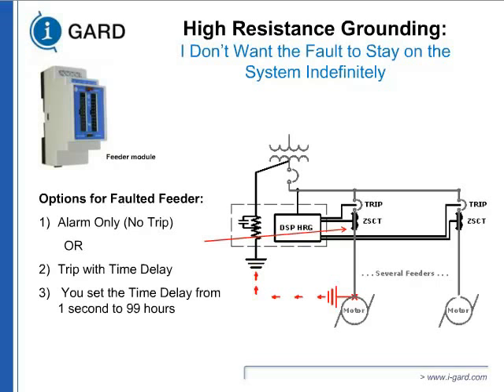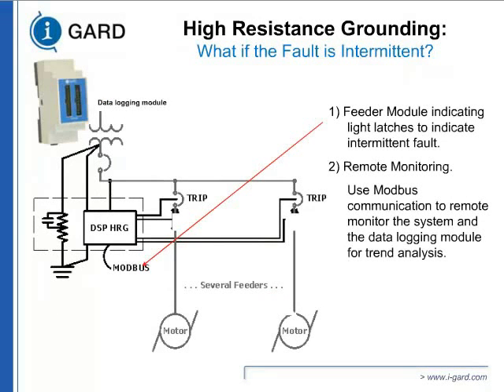What if the fault is intermittent? High resistance grounding normally may not catch it because it depends on picking up a relay. But now latch relays are available. They will catch that intermittent fault and tell you there was a fault in the system, even though the 480 volt fault will clear. 480, 600 volt faults will clear. Medium voltage will run into a phase-to-phase fault if not cleared, but a 480 volt fault will burn out. And so this gives you an option.